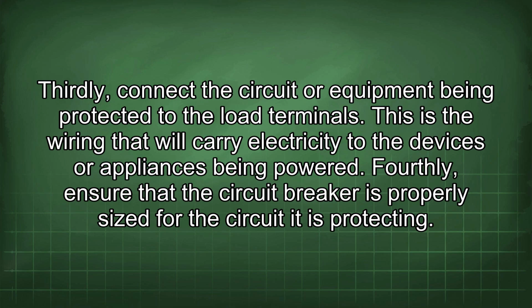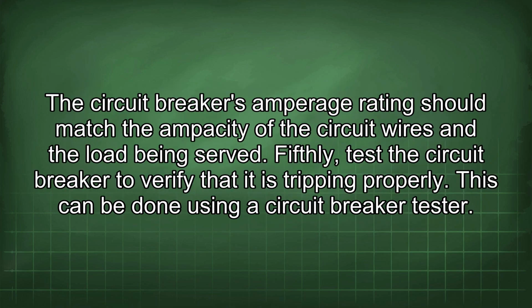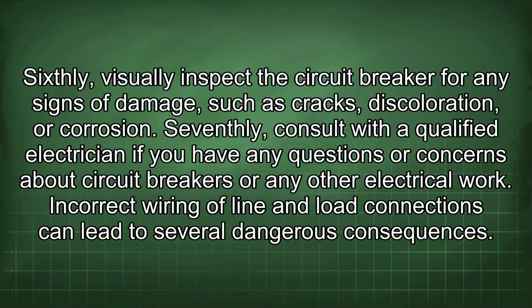Fourthly, ensure that the circuit breaker is properly sized for the circuit it is protecting. The circuit breaker's amperage rating should match the ampacity of the circuit wires and the load being served. Fifthly, test the circuit breaker to verify that it is tripping properly. This can be done using a circuit breaker tester. Sixthly, visually inspect the circuit breaker for any signs of damage, such as cracks, discoloration, or corrosion. Seventhly, consult with a qualified electrician if you have any questions or concerns about circuit breakers or any other electrical work.